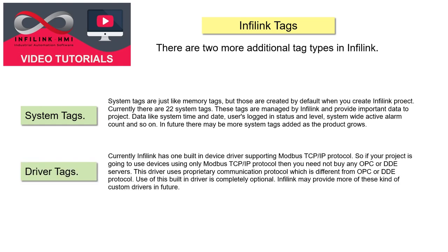Driver tags. Currently Infilink has one built-in device driver, supporting Modbus TCP/IP protocol. So if your project is going to use devices using only Modbus TCP/IP protocol, then you need not buy any OPC or DDE servers. This driver uses a proprietary communication protocol, which is different from OPC or DDE protocol. Use of this built-in driver is completely optional. Infilink may provide more of these kinds of custom drivers in future.